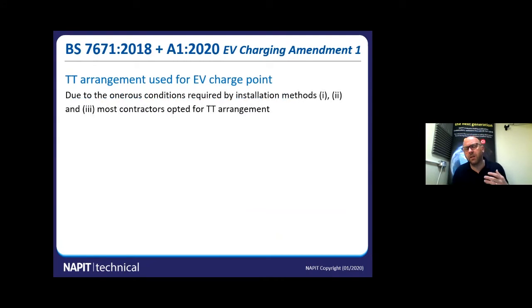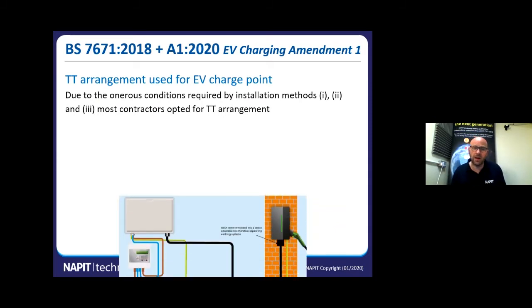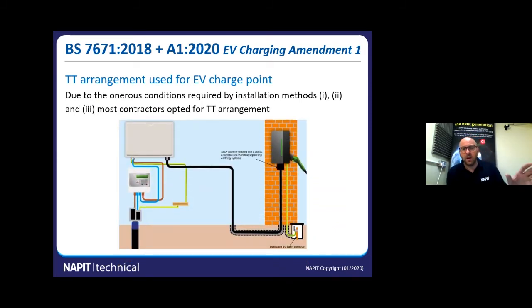Prior to that, the contractors out there would struggle to meet one of those 3, so they would look at a TT arrangement. We have a picture here. You can see we've got the TNCS at the service head there, and the circuit coming out to the EV charge point is using the TNCS, and then it's separated at the plastic box just below the charge point, and a dedicated earth electrode is used for the EV point. So that's absolutely fine. That's a TT arrangement, no problem. We're not going to get any problems from that PME system.